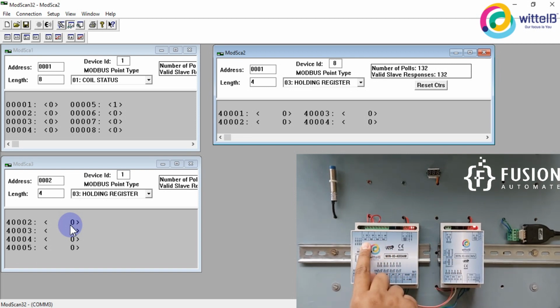So this digital output is associated with the coil status from 01 to 04. 01 is linked with the DO1, 02 with the DO2, 03 with the DO3, and 04 with the DO4. 05 is linked with the DI1, 06 with the DI2, 07 with the DI3, and 08 with the DI4. You have to remember this. And for our analog output card, 40,001 is linked with analog output 1, 40,002 with analog output 2, 40,003 with analog output 3, and 40,004 with analog output 4 of this Modbus IO card.